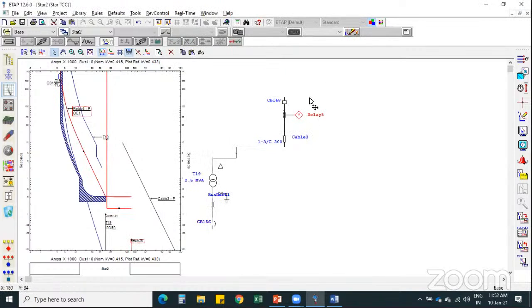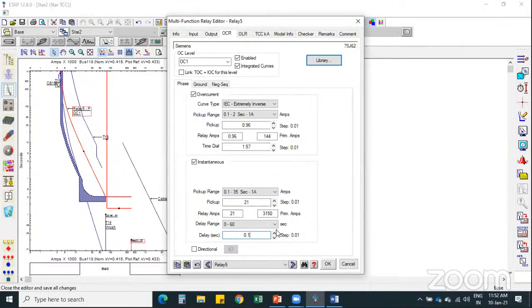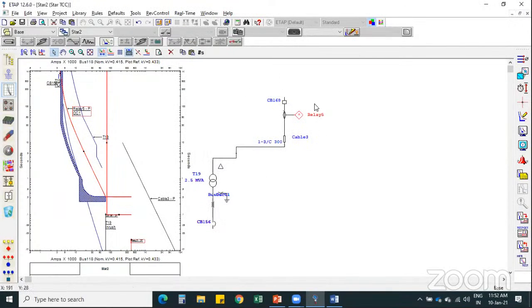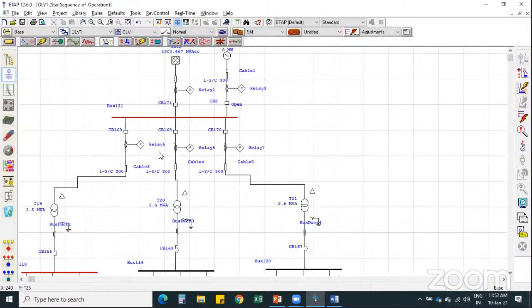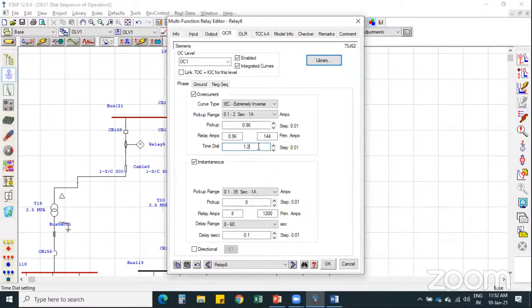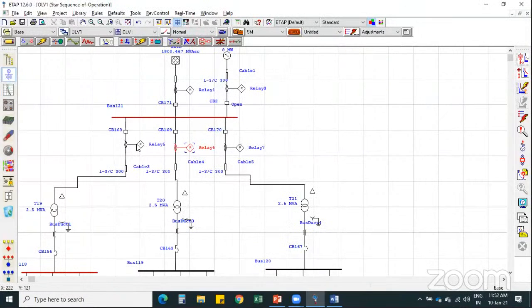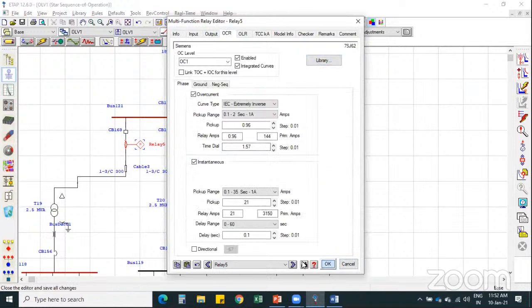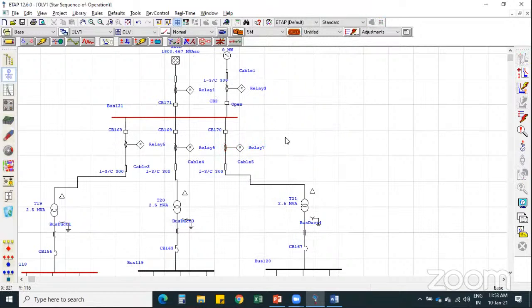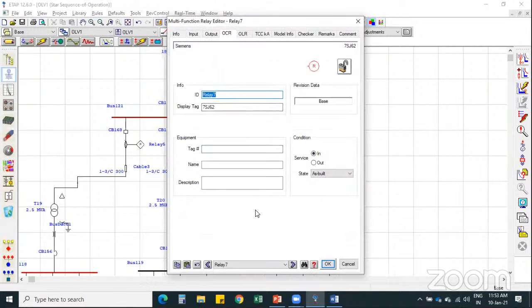Sorry, let's take 0.1 seconds only, such that as the voltage level changes, we can start these settings from the minimum value, that is 100 milliseconds, with a minimum time delay of 100 milliseconds. Accordingly, the relay settings have been adopted and changed. So the same setting will be changed here, 1.5, the 21 and 0.1 extremely inverse. We have taken 1.57. So similarly 1.57. As the ratings of all the transformers are the same, I am taking the same similar settings for all the transformers, and accordingly I am changing the parameters over here also.